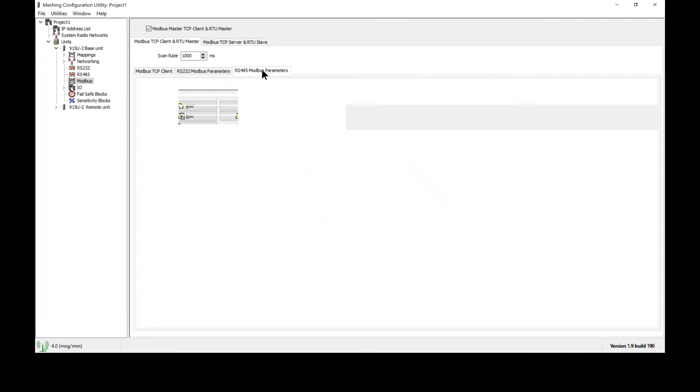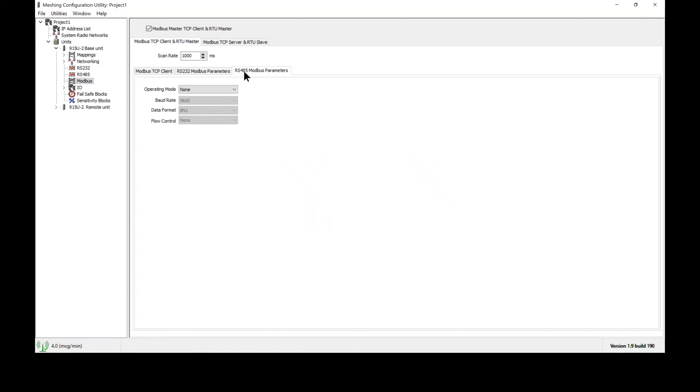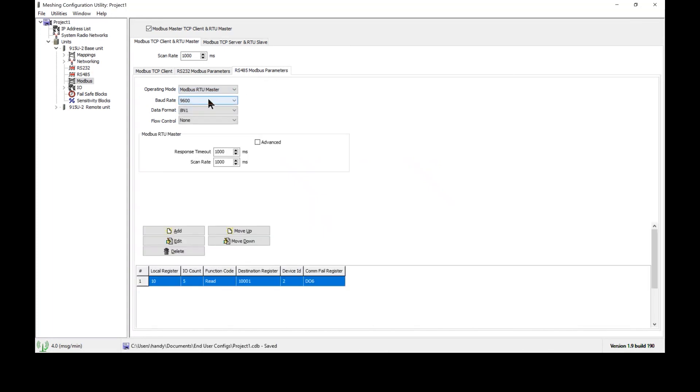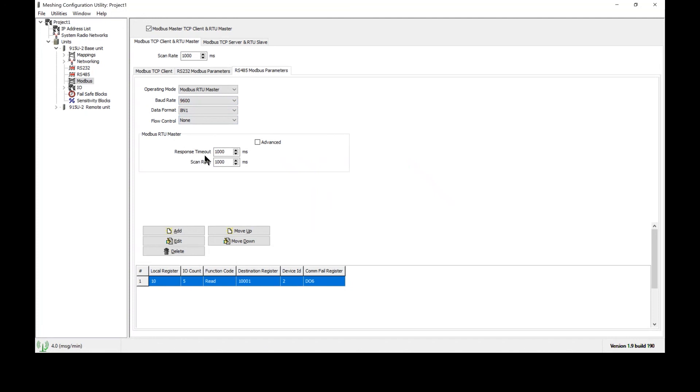If we had Modbus RTU then what we would need to do is we would need to select Modbus RS485 Modbus parameters and set the port for Modbus RTU master mode. Then we have to set the baud rate, data format, flow control to match what the PLC is, so these parameters must be the same on the radio as they are on the PLC. Next we have our scan rate and response timeout. These are going to occur once per second and the radio will wait one full second for the PLC to respond.